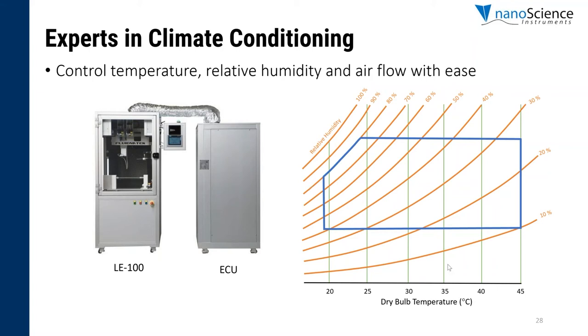We can actually operate from 18 degrees Celsius to 45 degrees Celsius, and humidity from 10 to 80%. For example, let's say you want to operate at 25 degrees Celsius; that means you will have a relative humidity capable from 30% all the way to 75%. Meanwhile, if you want to operate at really high temperatures in the chamber, like around 45 degrees Celsius, that means your humidity will be able to operate from 10% to 26%.